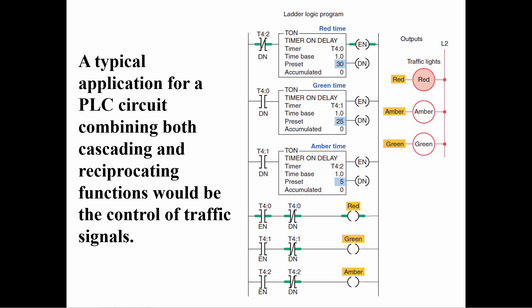This ladder logic program is designed to control the red, amber, and green lights of a traffic signal for traffic in one direction. The program uses three TON timer instructions in a cascaded and reciprocating arrangement. When the program first starts, all of the done bits will be zero. The examine-if-open T4:2/DN instruction on the first rung will be true and timer T4:0 will start timing.